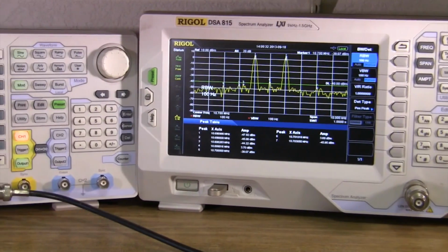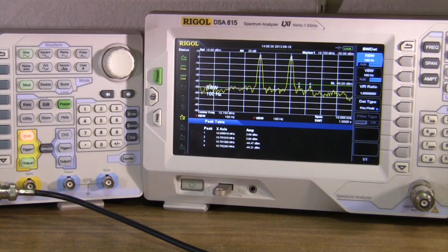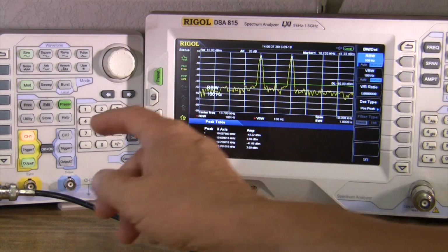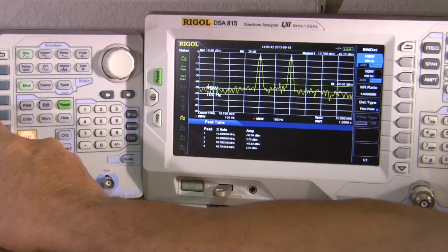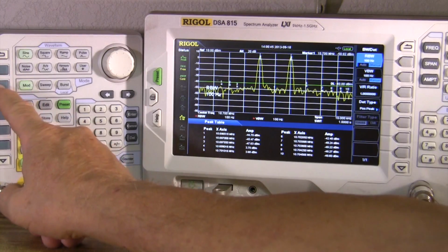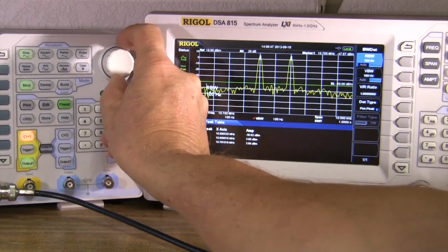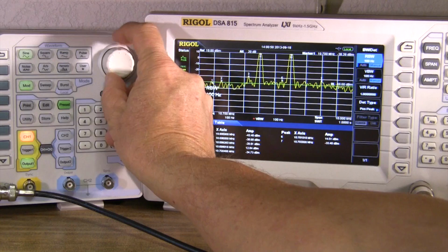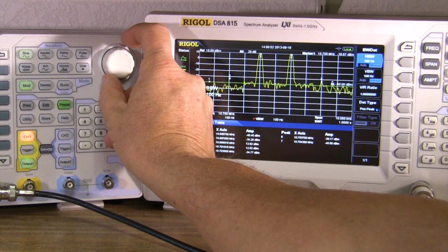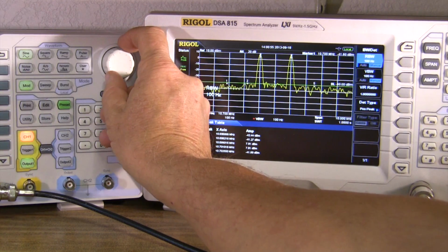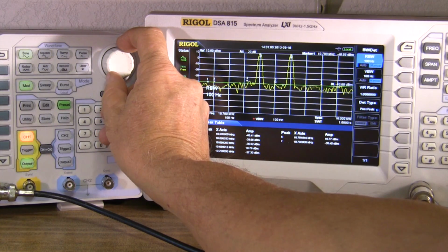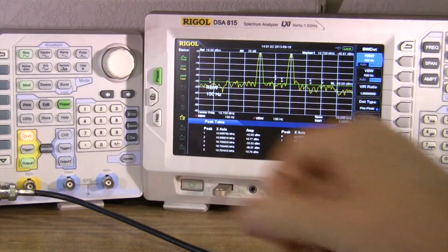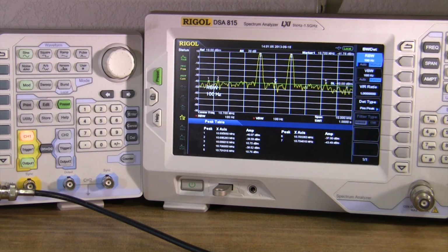What I'll have to do for that, let me crank this over here. And if I get a sine wave again here, and I'm already on the amplitude, as you can see here, if I crank that up some more, I can push that up to 10.76, so slightly above 10 dBm per tone.